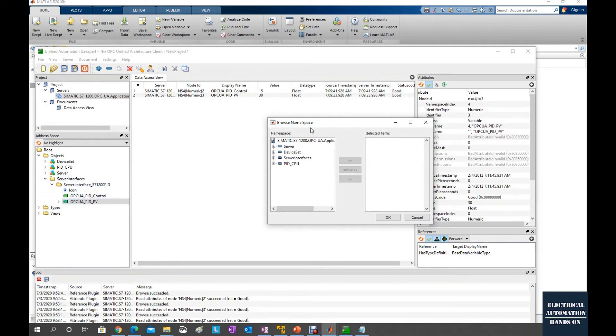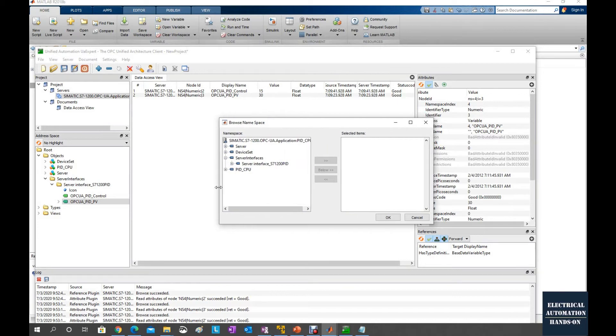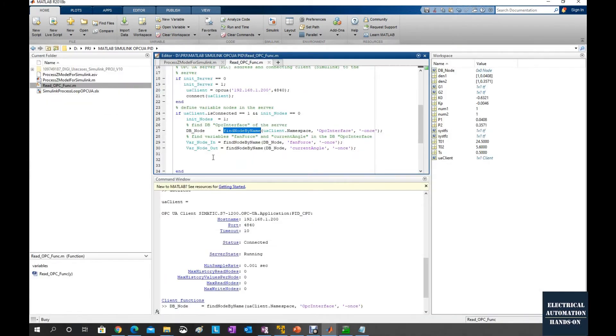Under this browse namespace window, let's expand the directory — we will find the same tag hierarchy and the two tags. So using browse_namespace, we can find the same tags from the OPC UA server, confirming this function works on the OPC client in MATLAB. However, using the name browser can have issues because tag names may have capitals, underscores, spaces, or other characters. That is why I prefer to use the second method: using the OPC node ID to browse the tag rather than the name.